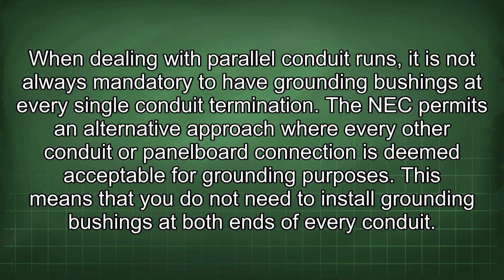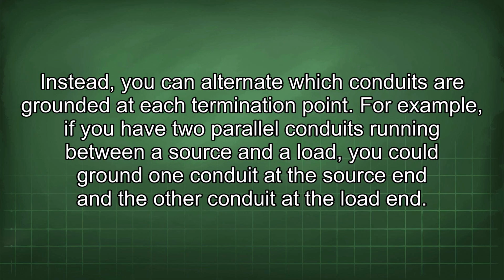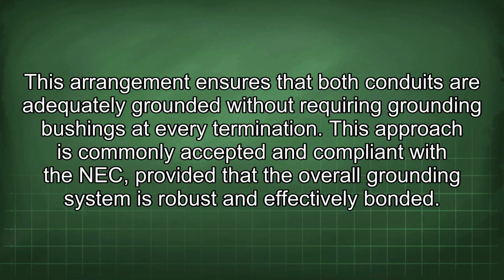This means that you do not need to install grounding bushings at both ends of every conduit. Instead, you can alternate which conduits are grounded at each termination point. For example, if you have two parallel conduits running between a source and a load, you could ground one conduit at the source end and the other conduit at the load end. This arrangement ensures that both conduits are adequately grounded without requiring grounding bushings at every termination.